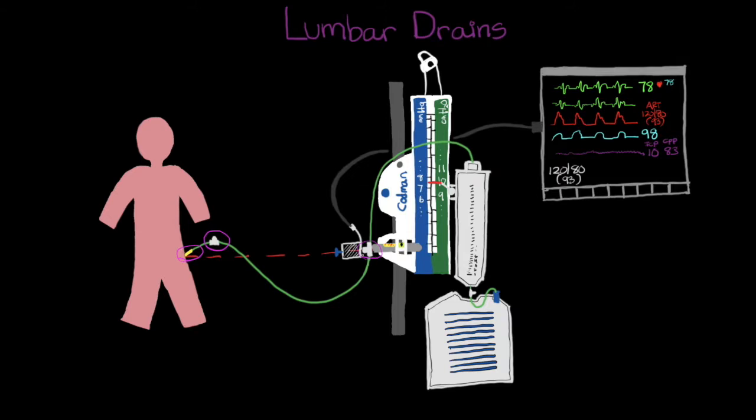To the right of the panel stopcock, you'll see our laser level, which is going to be used to ensure that we have this at the proper height. And to the left is going to be our transducer. And just like the transducers that we use for our other pressure monitoring, there's going to be a cable that comes off here, which we attach to a cable that will run all the way to our monitor here. Continuing along with the tubing from the panel stopcock, that will work its way over to the top of our drain, which is this big chamber here.